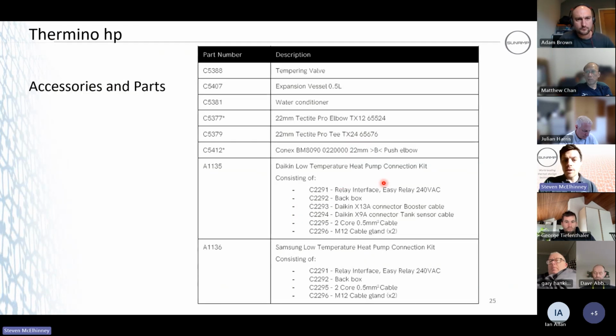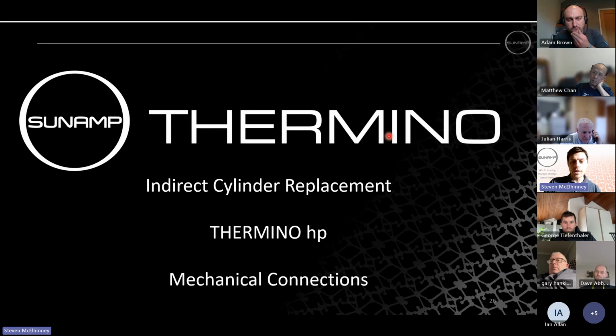If you're ever working with a Daikin or a Samsung, it will come with one of these accessory kits. So this is all electrical stuff: relay interface, back box, cables, things like that. You can request these parts from us. So that's your tempering valve, expansion vessel, a water conditioner if need be, Tectite elbows, a T-piece. You're probably going to use your own stuff, pipework fittings for that.